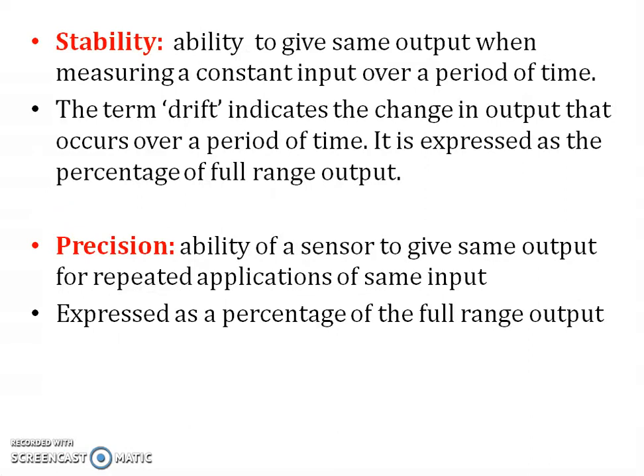Stability is the ability to give the same output when measuring a constant input over a period of time. The term drift indicates the change in the output that occurs over a period of time. It is expressed as a percentage of full range output. Precision is the ability of a sensor to give the same output for repeated applications of the same input. It is expressed as a percentage of the full range output.